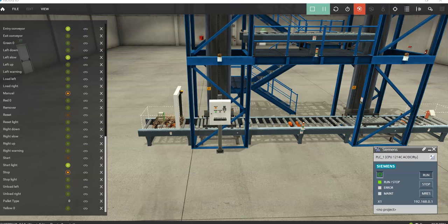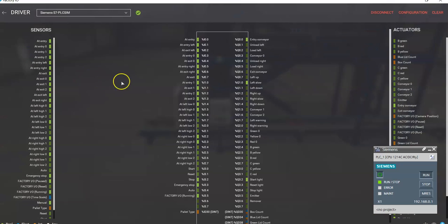And now just to show you what I was talking about before, if I go into the file drivers, you can see that we've got a couple things on, but we don't have the stoplight on. So we're not in the right condition to start it up again. So what we can do is go to this little screen here, stop it, wait a second or two, go back to run, and now everything is off except for that stoplight. This is the condition that you need to be in.